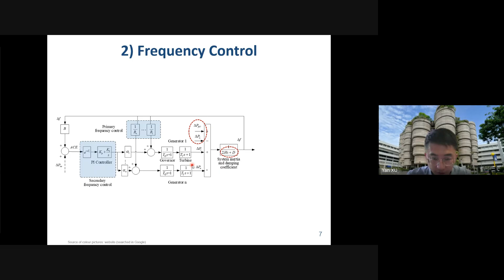This ACE will be input to this PI controller, and after that, this controller will issue the control signal for different generators, in terms of alpha 1, alpha 2, until alpha n. Each alpha will combine with the primary control signal and then go to the generator. Then the generator, after receiving these two control signals, will adjust the so-called governor speed, and will also adjust the input of the primary energy resource, let's say the gas input to the turbine, or for the hydro generator, the water flow input to the hydro turbine. So in the end, the frequency will be fully restored. So that is generally how the frequency is controlled in the power system.